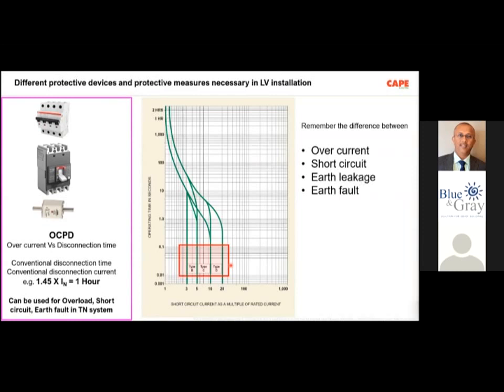shall be made in such a way that whenever there is an earth fault, the earthing system shall ensure that enough current, a large amount of current, flows through the circuit so that your protective device disconnects the fault. That is the fundamental requirement for earth fault protection. Whenever there is an insulation failure and an equipment is creating an earth fault, the circuit must be designed in such a way that enough fault current flows and it disconnects the supply. That is the fundamental of electrical safety.